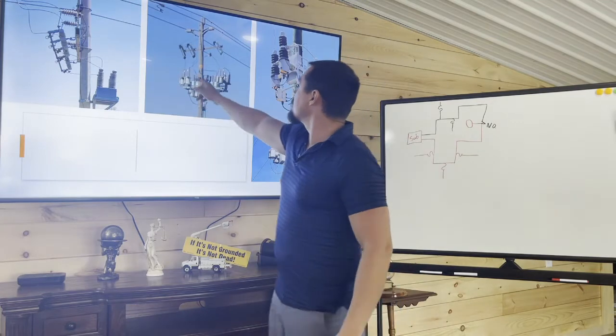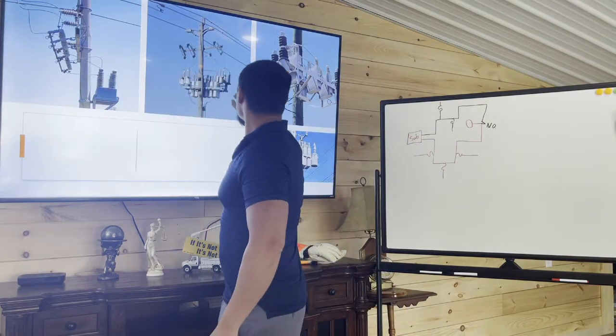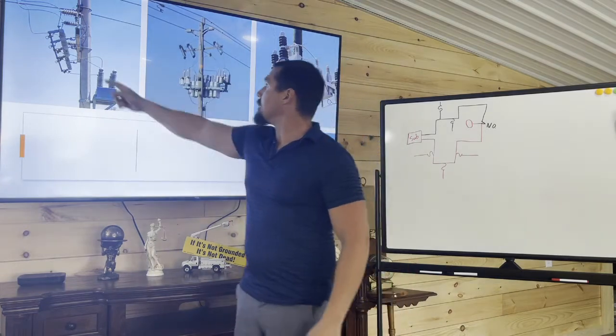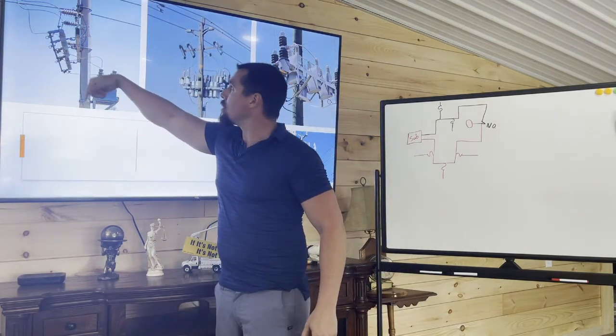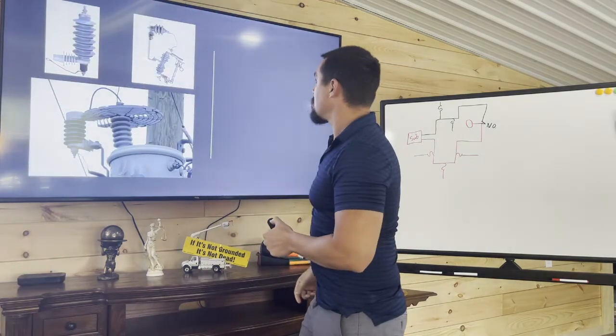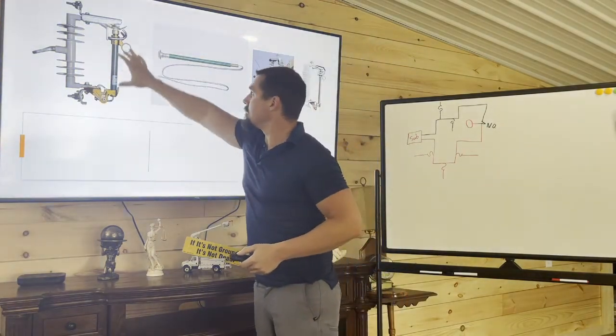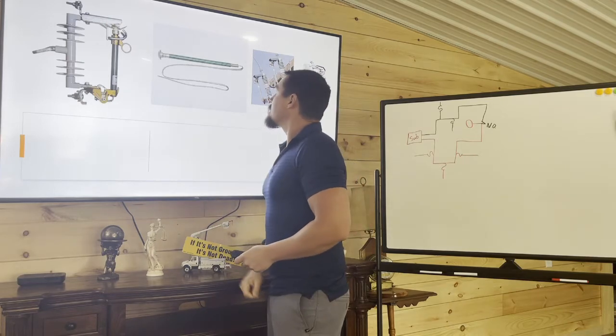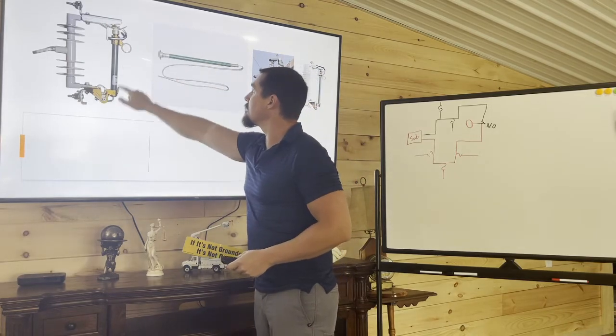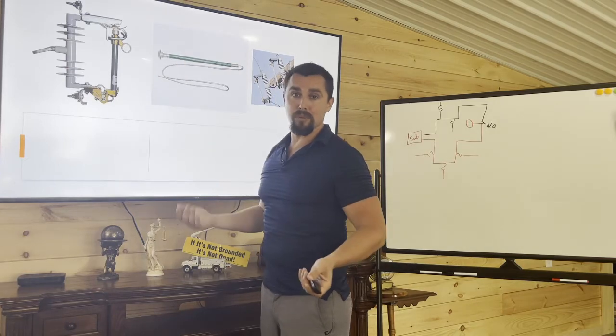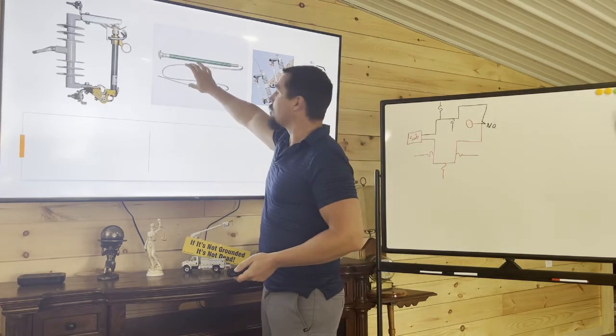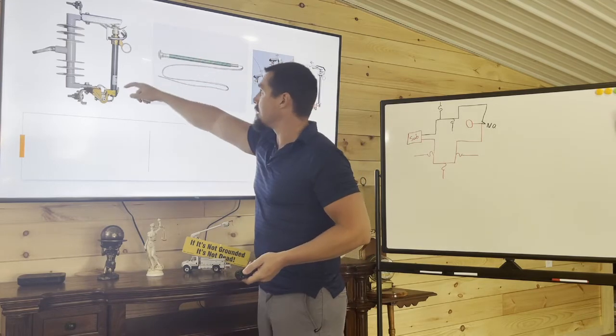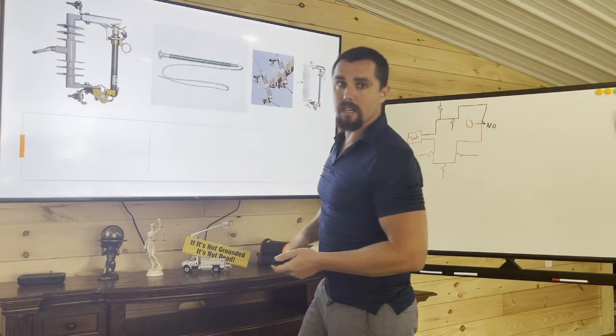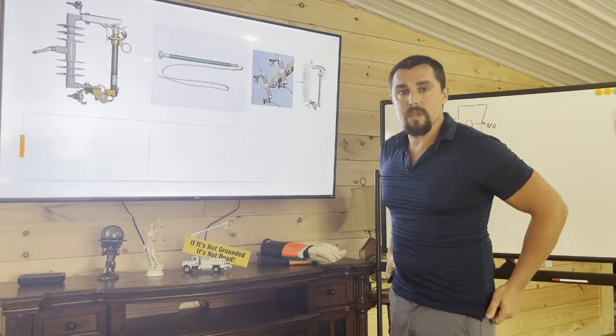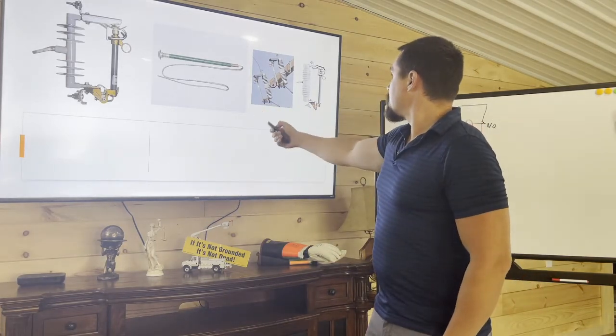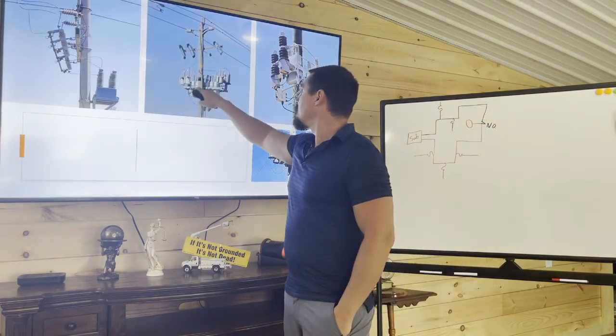As I was saying earlier, you have fuses going to each individual cell per phase. If these fuses blow, essentially the door will hang down. This is the fuse door, as we call it, and this is a fuse link, which goes inside that door. Whenever you hear a loud boom right before an outage, this is what essentially explodes inside the door. The door will hang down, letting the lineman or troublesman know there's an issue here. So this is what feeds the capacitor banks.